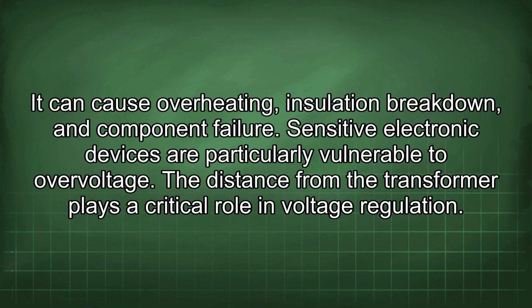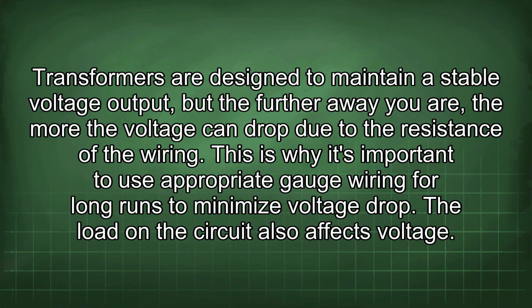The distance from the transformer plays a critical role in voltage regulation. Transformers are designed to maintain a stable voltage output, but the further away you are, the more the voltage can drop due to the resistance of the wiring. This is why it's important to use appropriate gauge wiring for long runs to minimize voltage drop.